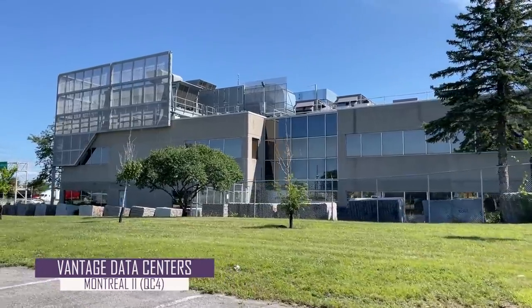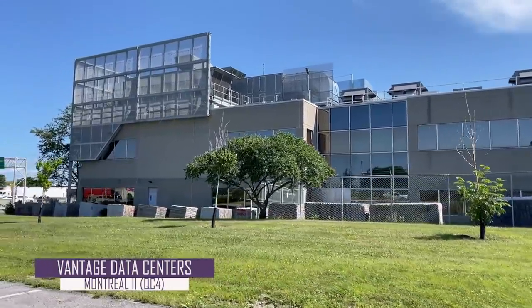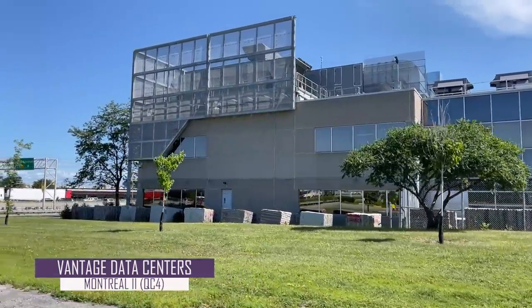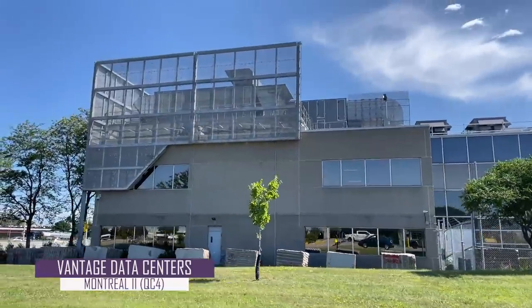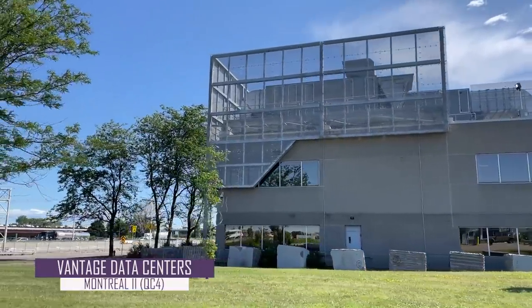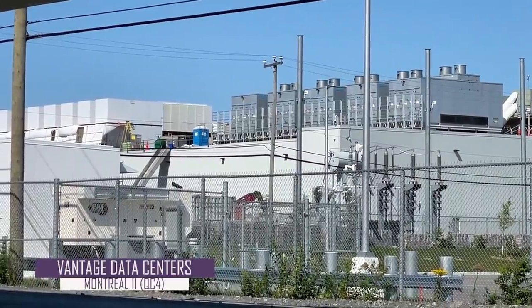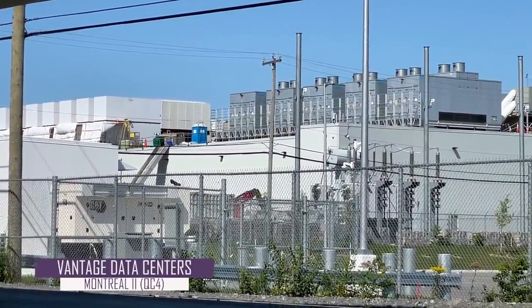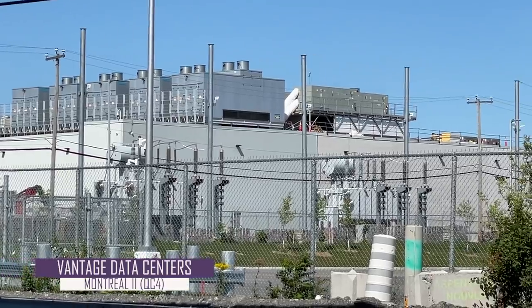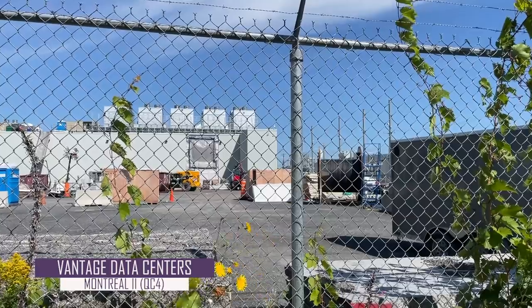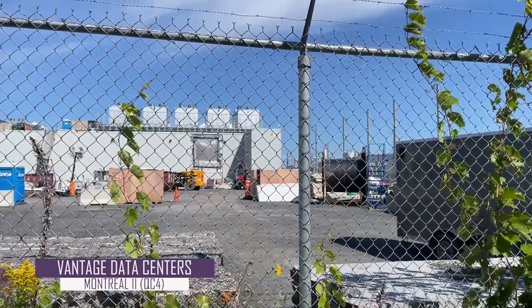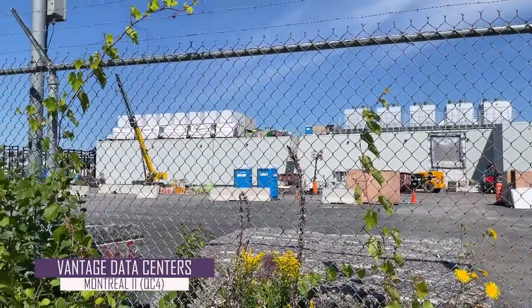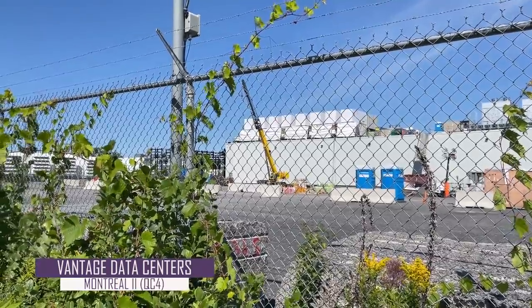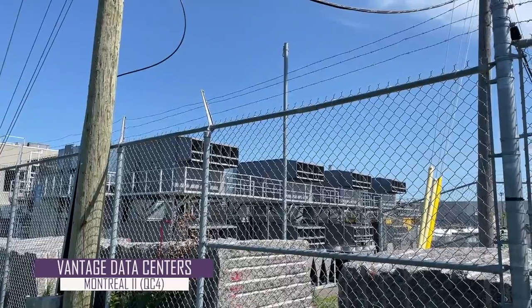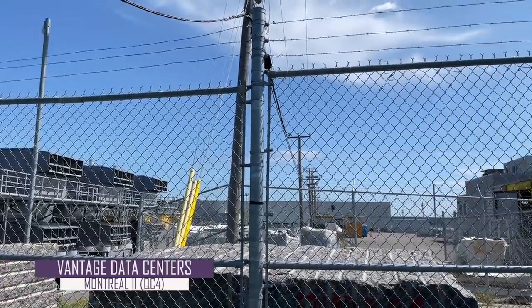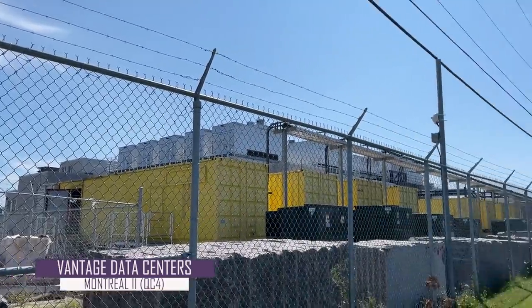Presently, Vantage has built 25 megawatts across 2 existing facilities with 24 megawatts of incremental capacity available by constructing one more building. Montreal 2 is fed by 2 25 kilovolt feeders and a dedicated 120 kilovolt substation. In terms of connectivity, the data center has 6 distinct and physically diverse entrances, which connect into 4 Meet Me rooms. Inside these Meet Me rooms is access to more than 10 regional, national, and international carriers.